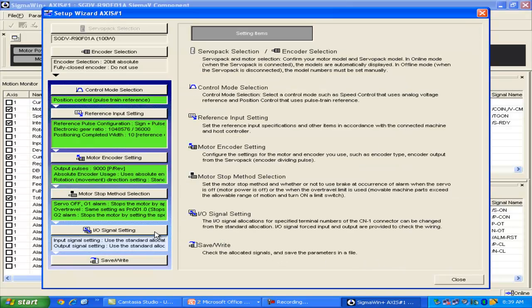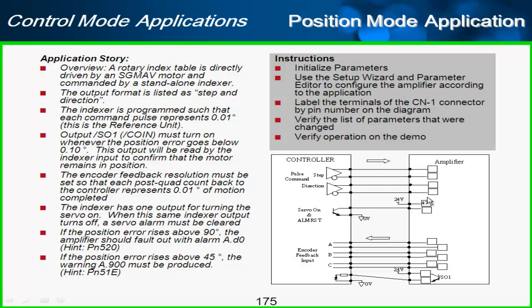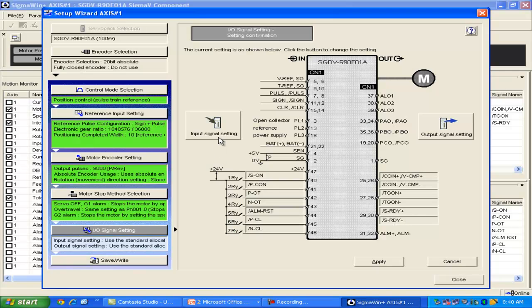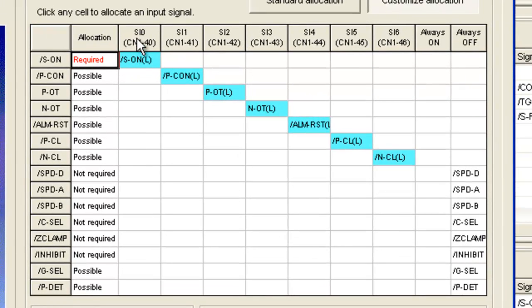Now for the I/O signal setting. For inputs, we see that the amplifier input servo on should also take the function of alarm reset when the servo on signal turns off, or when this input turns off. So I'll go into my input signal settings, and you see that I already have servo on, but alarm reset is on pin 44. So I can move that over and make it on the same pin.